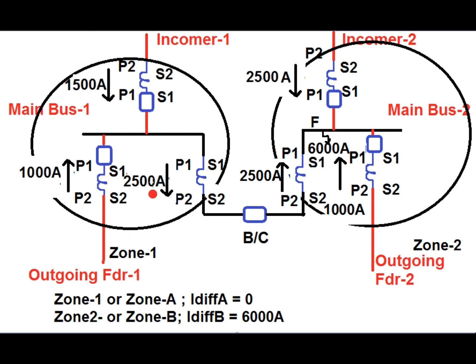Under the fault at main bus 2 condition, the zone 1 or zone A differential current is 0. Outgoing feeder 1 carries 1000 amperes from P2 to P1, incomer 1 carries 1500 amperes from P2 to P1, and 2500 amperes flows from P1 to P2 from main bus 1 towards main bus 2 via the bus coupler CT. Since the sum of the first two currents is exactly opposite to the bus coupler CT current, the zone A differential current is 0 and zone 1 remains under stable condition.